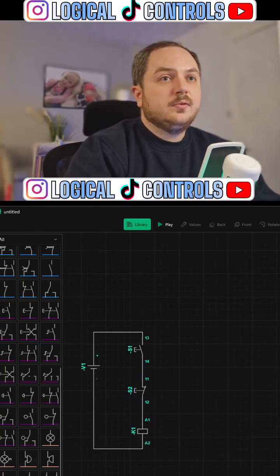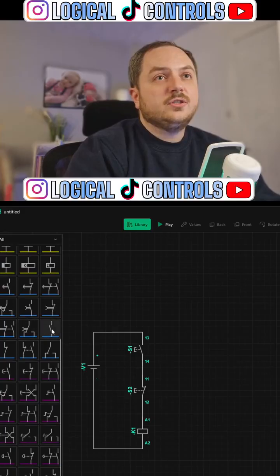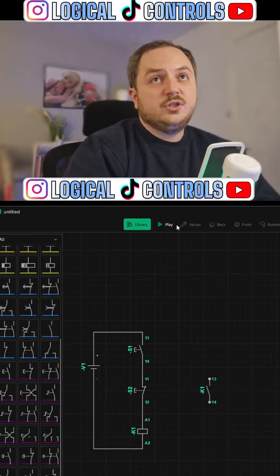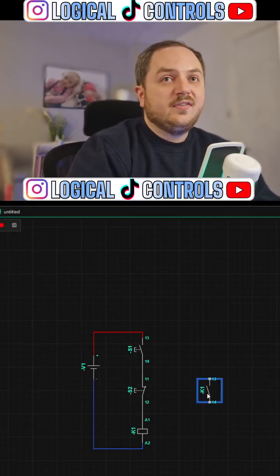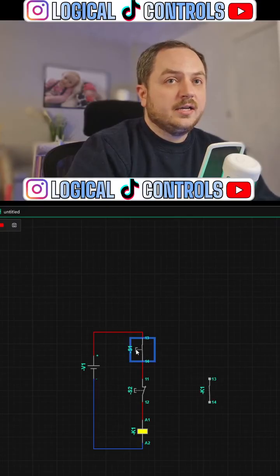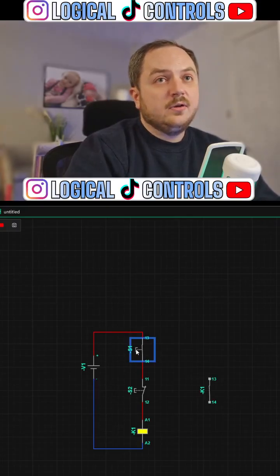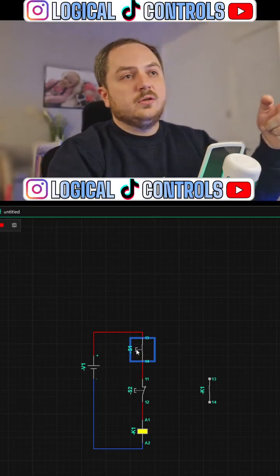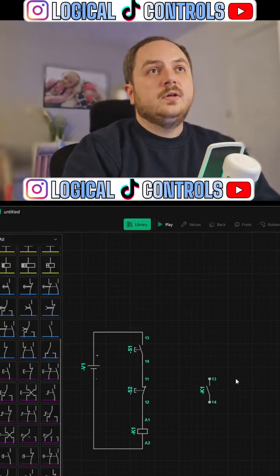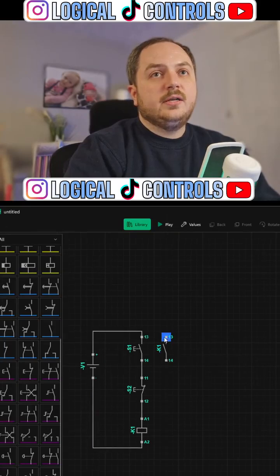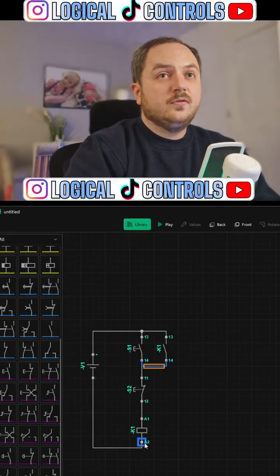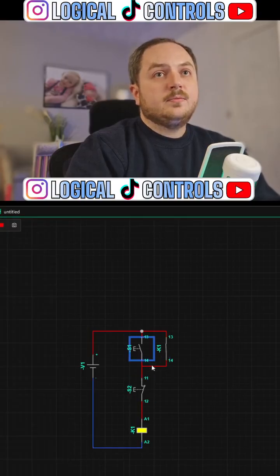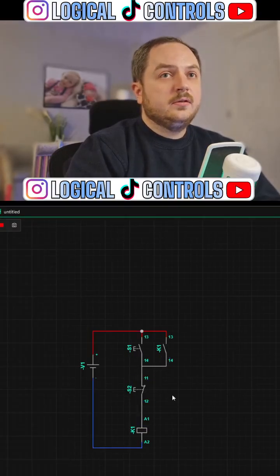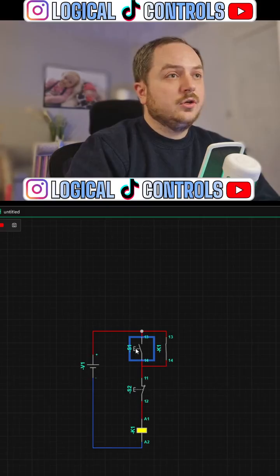Start and stop. K1 needs a contact of itself just to latch it in. Just to show you what I was on about earlier - if I don't put the latch in, I can energize the relay K1, but the minute I let go it de-energizes, which is no good. You don't want to be stood holding the button forever. So what we do is put in a parallel contact of the relay itself - K1, K1. It holds itself in, and then I use S2 to stop. Start and stop, that's it.